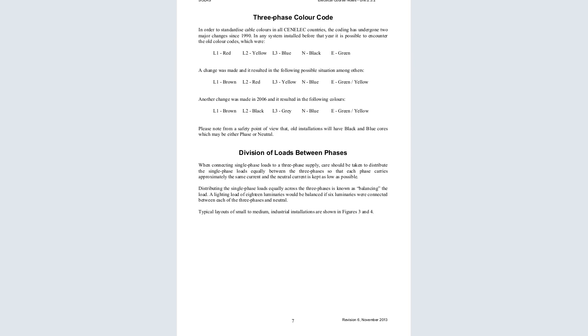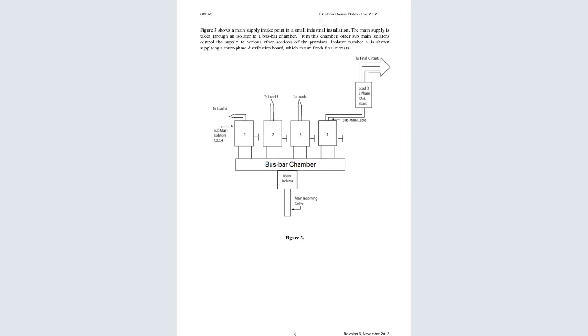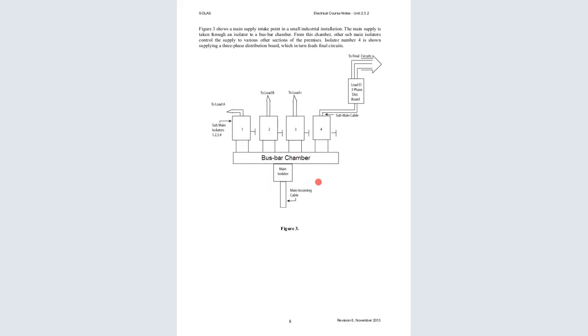A lighting load of 18 luminaires would be balanced if 6 luminaires were connected between each of the three phases and neutral. Typical layouts of small to medium industrial installations are shown in the figure. Let us go to the figure. So this is balancing the loads to the circuits.